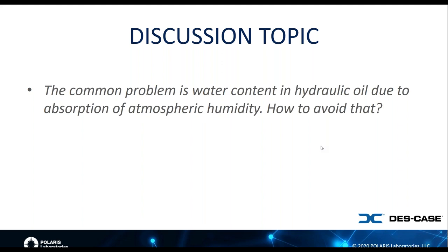It does, but on the oil analysis side, I would say also let's be cautious about how we measure the water content, right? There are a lot of different tests that we can use to measure water in hydraulic fluids, and we want to make sure that we're using the correct method. The Karl Fischer method, particularly using a co-distillation apparatus, which eliminates in hydraulic fluid the ZDDP additives, sometimes can show a false positive of water. So we want to make sure that we're using the Karl Fischer method, including the co-distillation option, which will allow you to get a very accurate idea of how much moisture you actually have in that fluid.